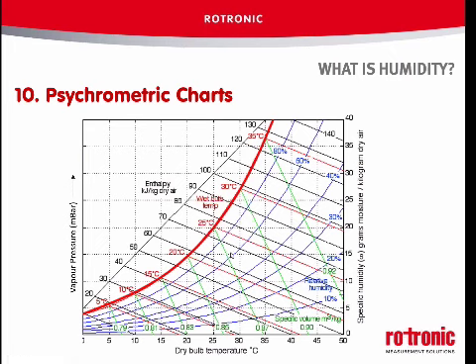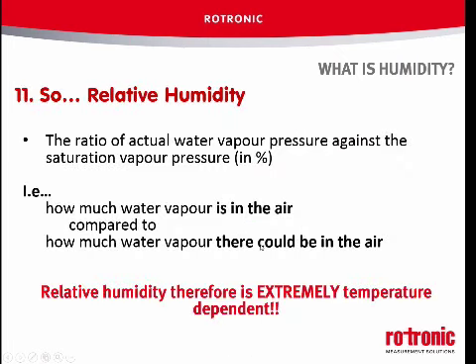If you're taking cold air that has a nice high RH, maybe 80%, 60% here at 10 degrees, and we move it up to 23 to keep everyone happy, we can see straight away the humidity goes low. So if you were controlling on humidity alone without any intelligence, you'd have the dryers going absolutely crazy, heating the air up, and then it'd be totally way too dry. So you need to understand that as air moves and temperatures change, humidity is often doing strange things, but very predictable things. That's the key thing.